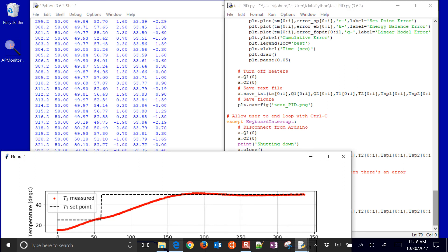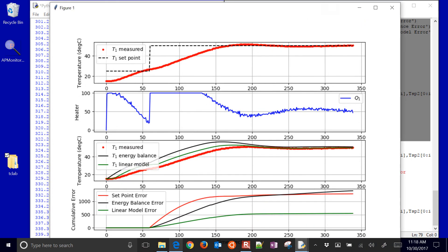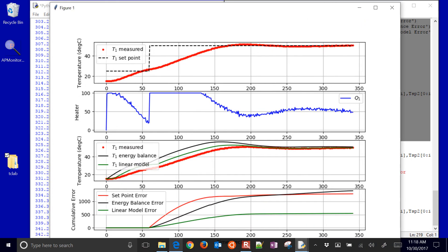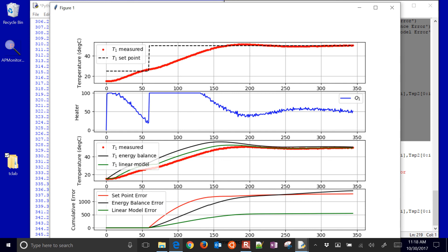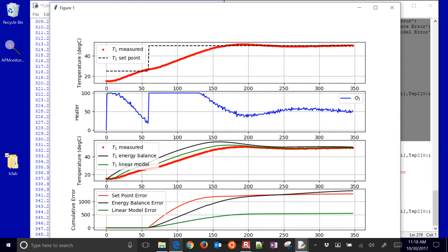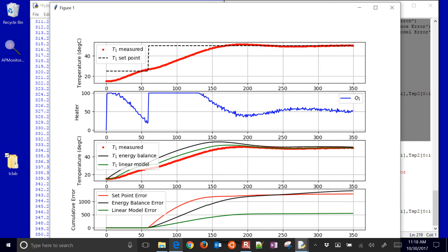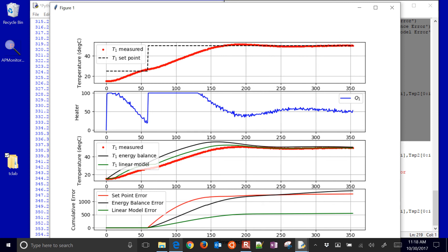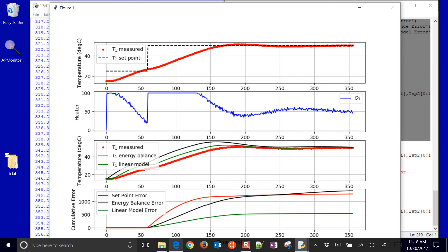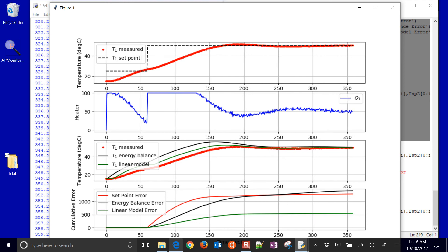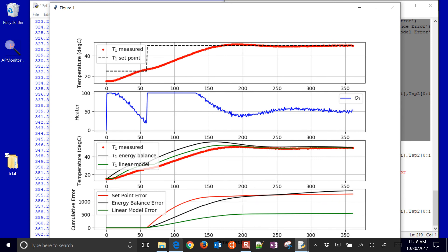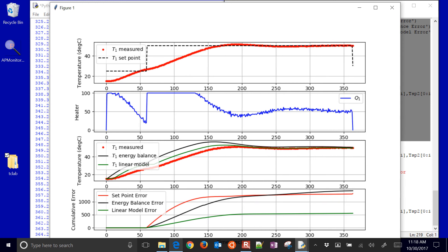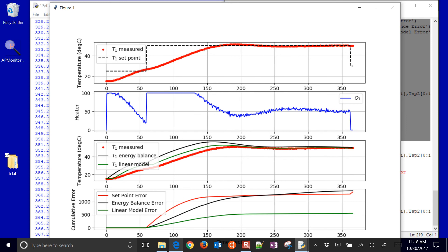I'll bring it back up here. So you can see it's following the set point fairly well. Just slight overshoot there. You'd want to quantify that. Looks like only about a two degree rise over the set point there. So that's pretty good. It looks like it's less than the 10% overshoot. You want to get it to be less than 2.5 degrees Celsius overshoot over the set point there.